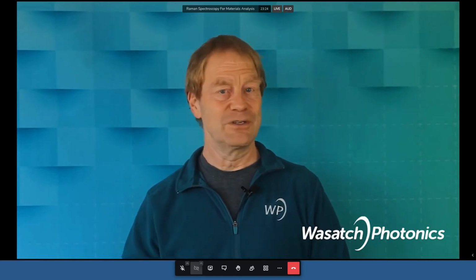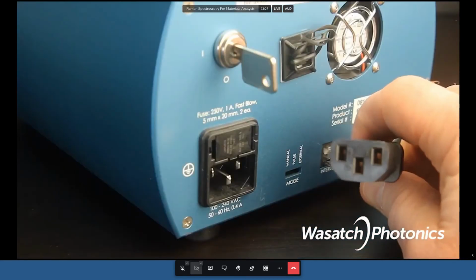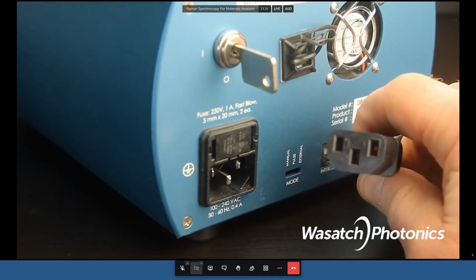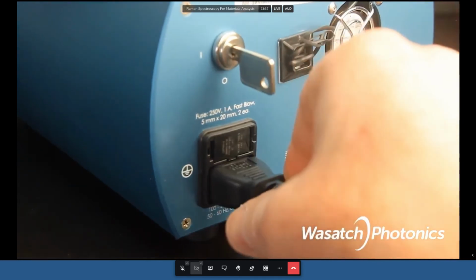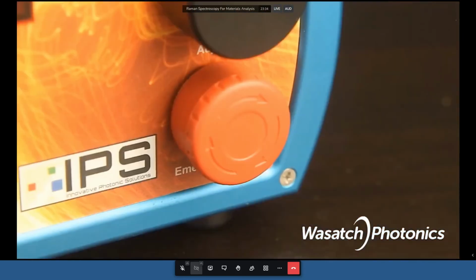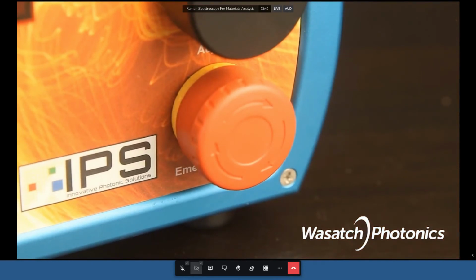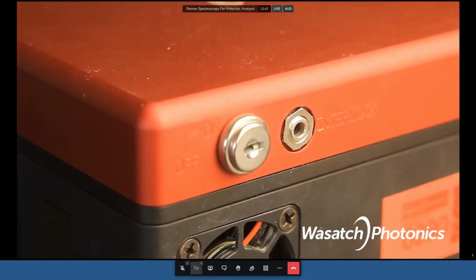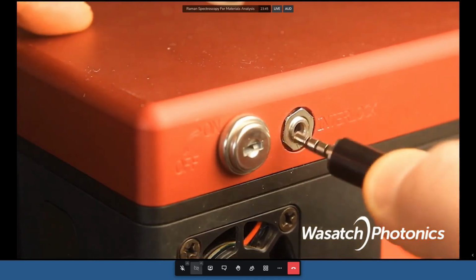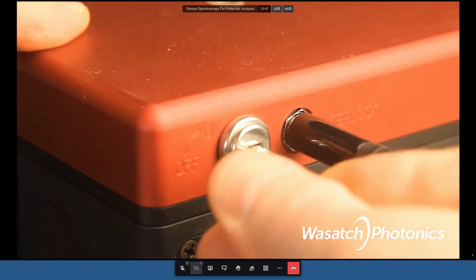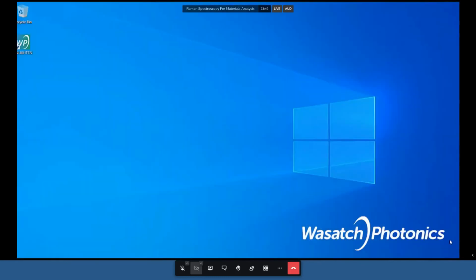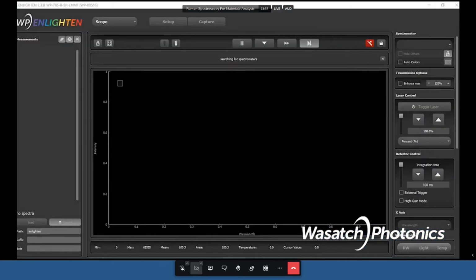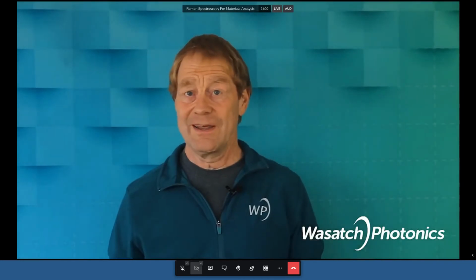We're almost done. Now we just need to get the laser ready. If you're using an external laser, you need to plug the power cord into the back of the laser. Turn the key, which is also on the back. Rotate the red safety button on the front to release the button in case it was pushed in. If you're using a spectrometer with an integrated laser, plug in the key and the interlock override, which is provided. Then turn the key. Now we can start up the Enlighten software. Double-click on the icon on the desktop. Enlighten will find your spectrometer and start reading the baseline automatically. That was really it for the setup.